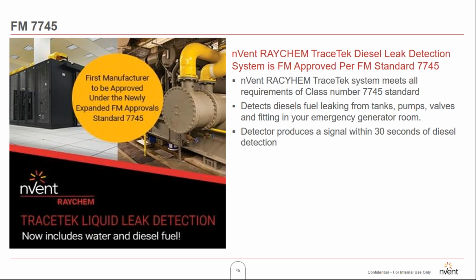nVent RAYCHEM TraceTek system was the first system to meet all the requirements to qualify for FM 7745 standards. These systems typically detect diesel fuel leakages from tanks, pumps, valves, and fittings, which we normally use for diesel storage and diesel generators for electricity generation purposes in buildings. These FM approved probes can give a signal within 30 seconds of a typical diesel leak which has happened.